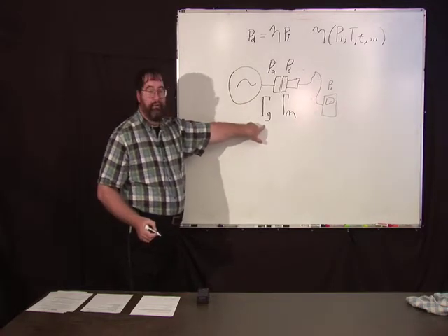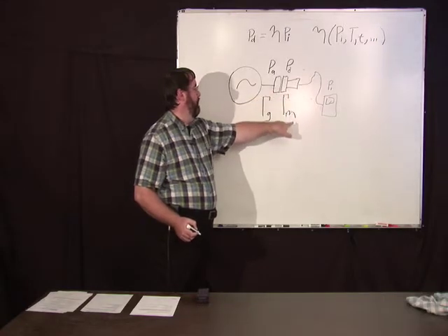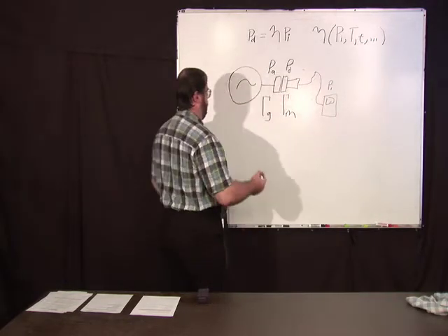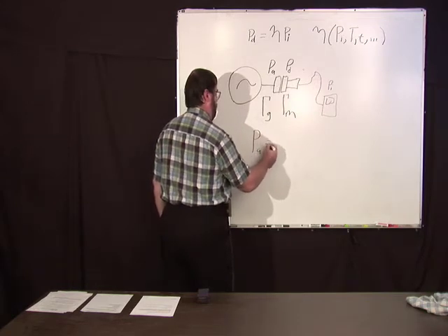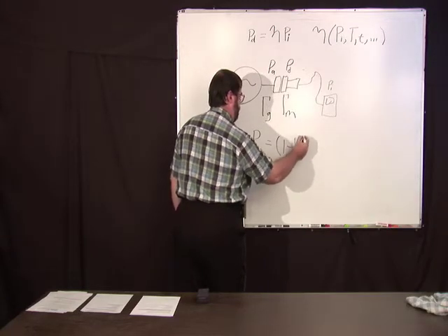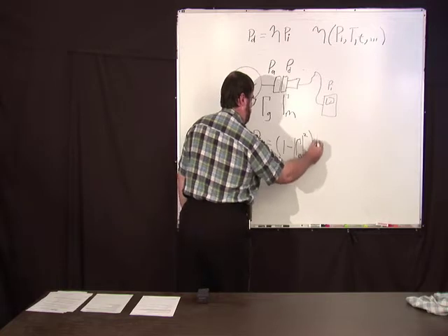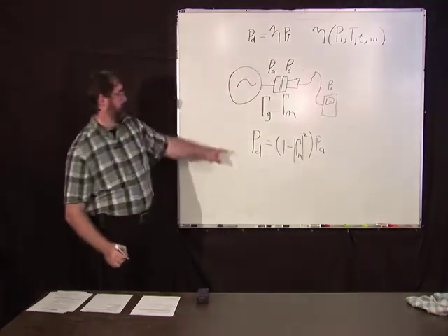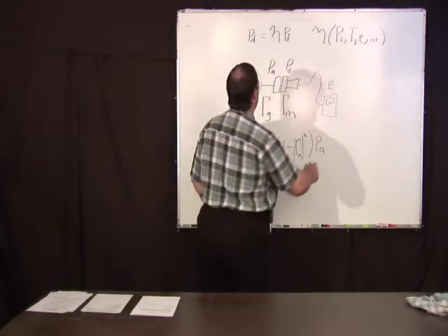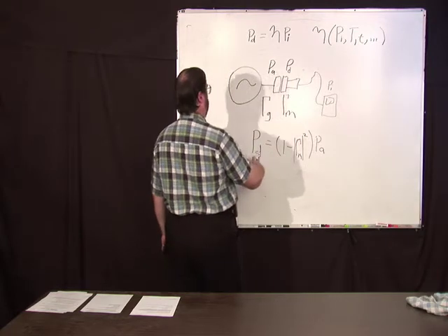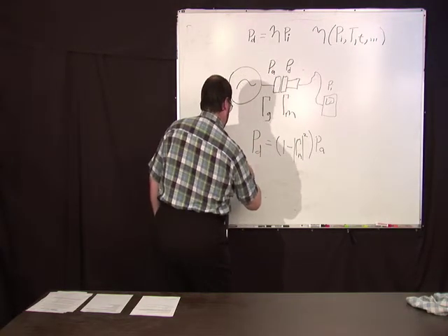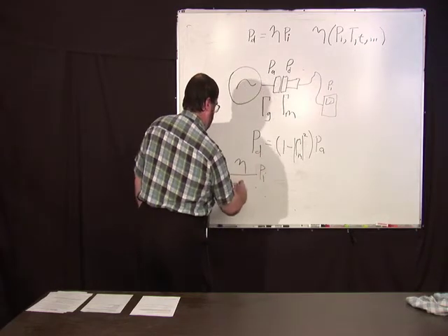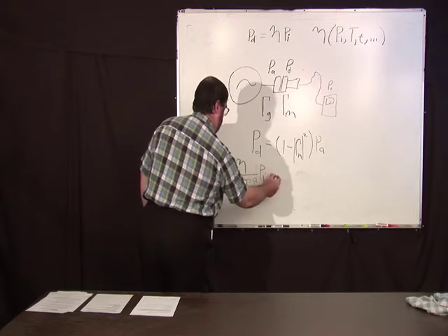Now, we don't typically want to measure the delivered power, what we're really interested in is what's called the available power. And that's the power that would be delivered to a matched load when connected to this port. That's not going to be the same as the delivered power. Now if gamma g was zero, the only reflection was from the sensor, then the delivered power is going to be one minus gamma meter squared times the available power.